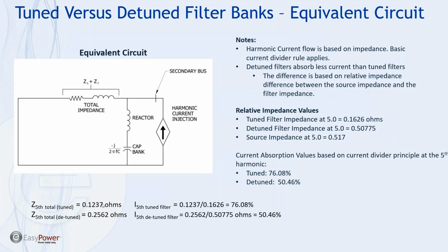So I did some calculations here. We're doing the parallel sum rule, okay, to get a Z total impedance, and we can do this at the fifth harmonic. And I did that for the tuned filter, and I also did it for the detuned filter. Once we know the total impedance at this point, which is a combination of this value and this value using the parallel sum rule, we can calculate the harmonic current flow into the filter here based upon taking the Z5 total tuned impedance value of 0.1237, and then dividing by the fifth filter impedance, which I have noted up here. Okay, and in that way we can come up with a value of percent, or what percentage of current will flow into the filter branch versus what current will flow into the source impedance.